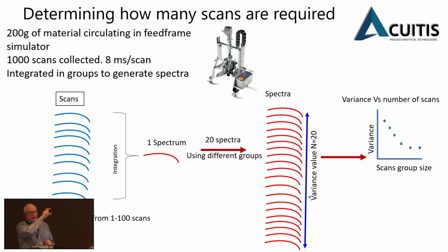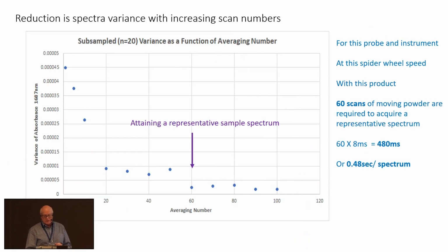So in that way, we can look at how, if we take different numbers of scans and average them into a spectrum, how many scans do we need to get a stable spectrum? Well, here's the curve, and you can see as we increase the number of scans, the spectrum that we're collecting with the probe stabilizes, and we know that we're going to get a stable representative spectrum. And I think it's very important that people understand that you do need to do this for every product. In fact, this curve relates to one wavelength, and that's the wavelength of that particular API. In fact, it's saccharin. So it's an empirical way to use the simulator to determine when you're going to get stable representative sampling in that type of feed frame environment.